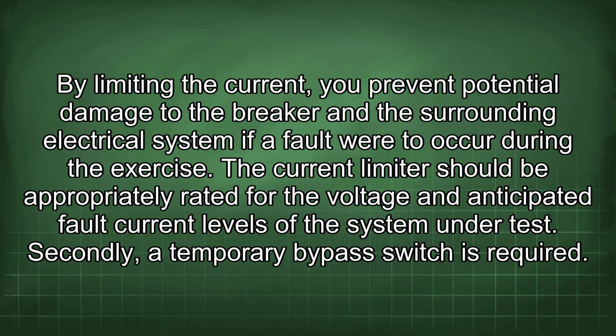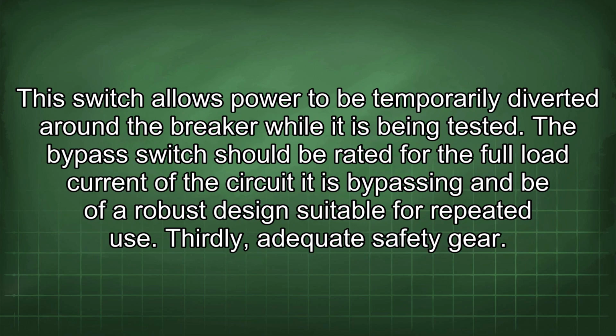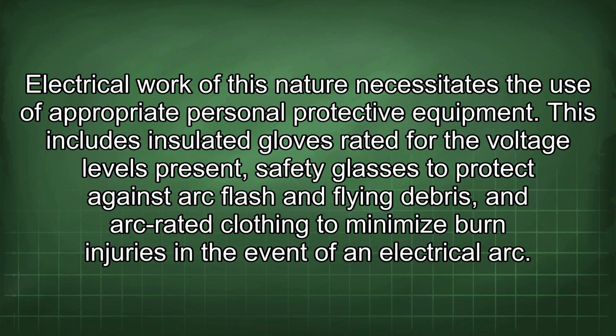Secondly, a temporary bypass switch is required. This switch allows power to be temporarily diverted around the breaker while it is being tested. The bypass switch should be rated for the full load current of the circuit it is bypassing and be of a robust design suitable for repeated use. Thirdly, adequate safety gear. Electrical work of this nature necessitates the use of appropriate personal protective equipment. This includes insulated gloves rated for the voltage levels present, safety glasses to protect against arc flash and flying debris, and arc-rated clothing to minimize burn injuries in the event of an electrical arc.